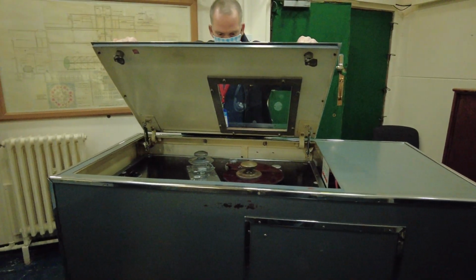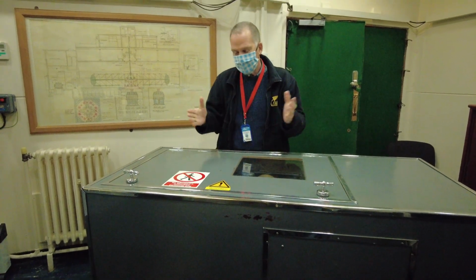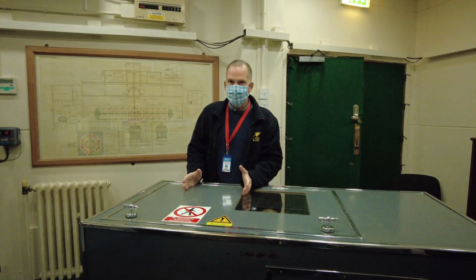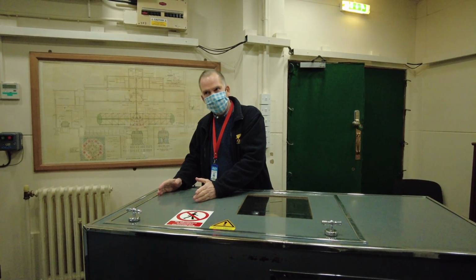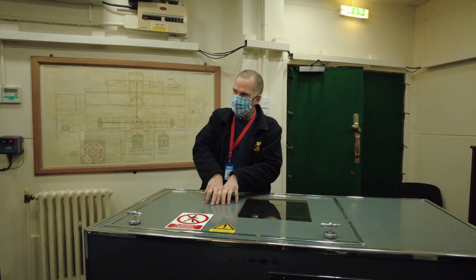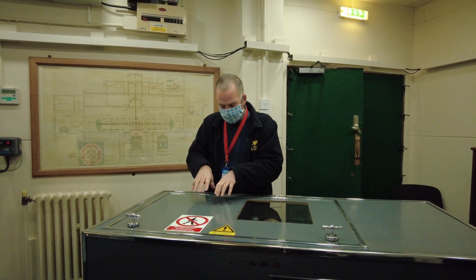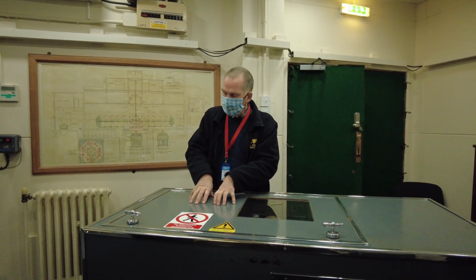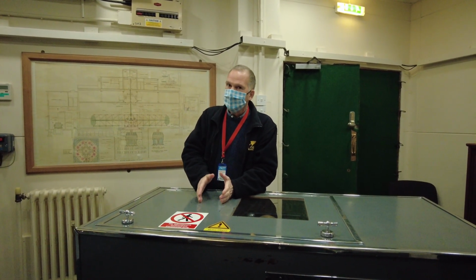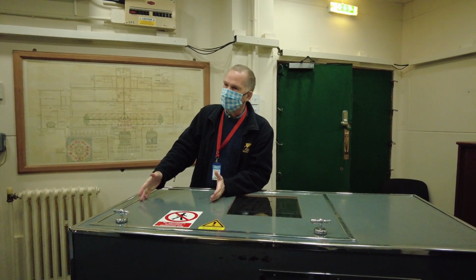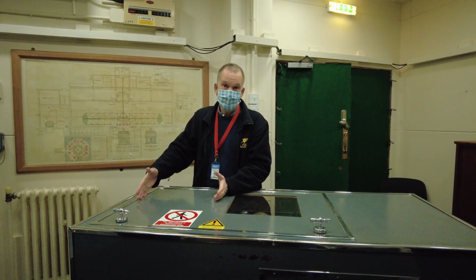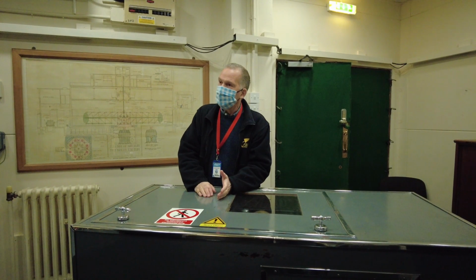One of the most important things about a centrifuge isn't what G it goes up to, it's how fast it gets there. And this accelerates at 1G per second. So if you're sitting still before the beginning of the run, you're already at 1G. So it takes 8 seconds to get to 9G, put on the extra 8, yeah, and then 8 seconds to come back again.